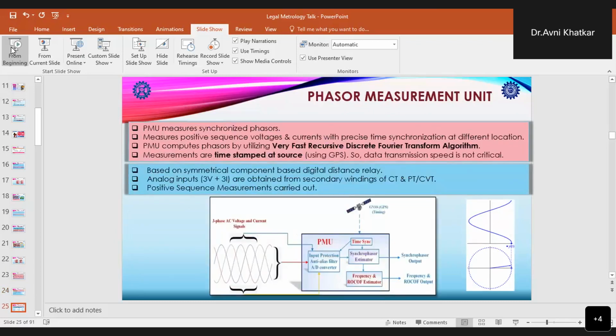So now what is this PMU? A PMU is actually a device, or it can also be a function in a multifunction device, which can produce synchronized phasors, frequency and rate of change of frequency, that is ROCOF, estimates for the voltage or current signals and a time synchronization signal. These phasor measurement systems actually trace their origin to the development of SCDRs, that is symmetrical component distance relays, of the early 1970s.